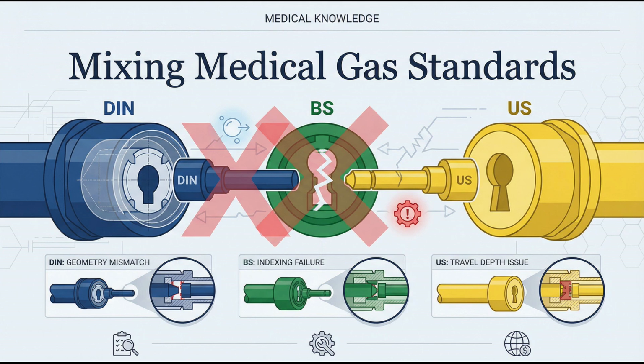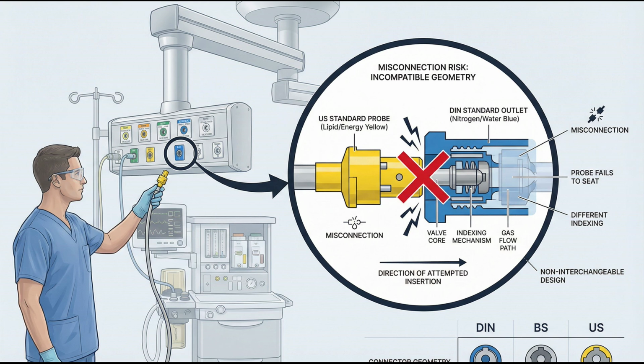Mixing medical gas standards. A brand new operating room sits ready. The medical gas installation looks perfect. But when the anesthesia machine is connected for commissioning, the probe won't fit. The project grinds to a halt. Why did this happen?